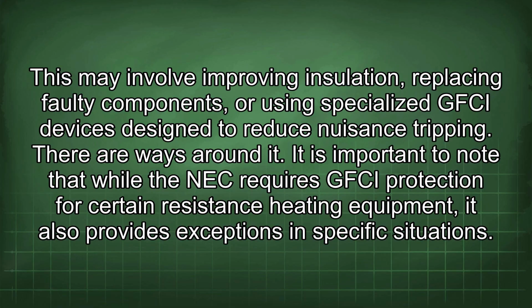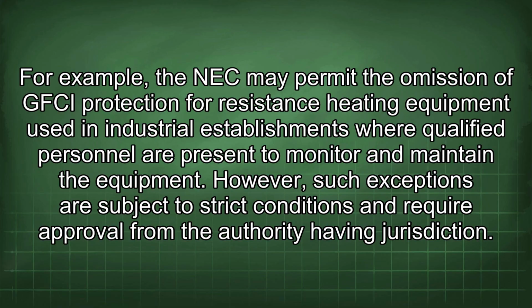It is important to note that while the NEC requires GFCI protection for certain resistance heating equipment, it also provides exceptions in specific situations. For example, the NEC may permit the omission of GFCI protection for resistance heating equipment used in industrial establishments where qualified personnel are present to monitor and maintain the equipment. However, such exceptions are subject to strict conditions and require approval from the authority having jurisdiction.